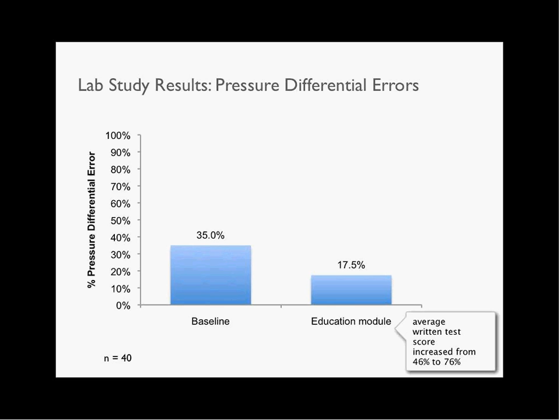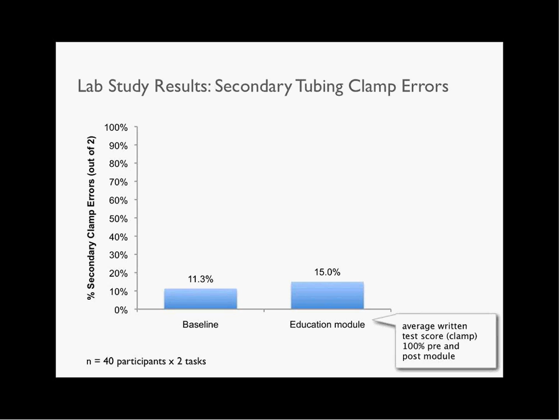Now, looking at secondary tubing clamp errors in the baseline condition, errors were common, but unlike pressure differential errors, the study results suggest that secondary tubing clamp errors are not a result of a gap in nurses' knowledge. In the test scores, nurses scored 100% before and after watching the module, which highlights that all nurses were actually aware of the need to open the secondary clamp, but were limited due to a lack of attention and or insufficient feedback from the infusion pump setup. We identified that some errors can be improved with education, but others, like this one, cannot.